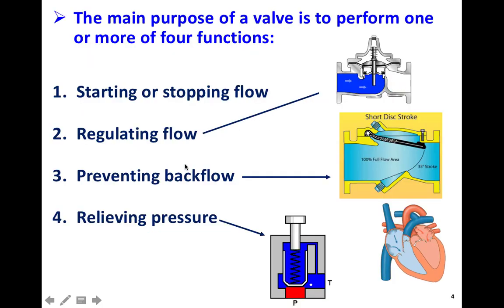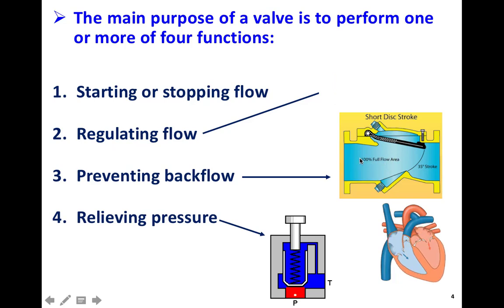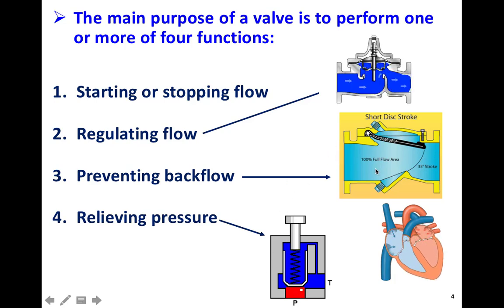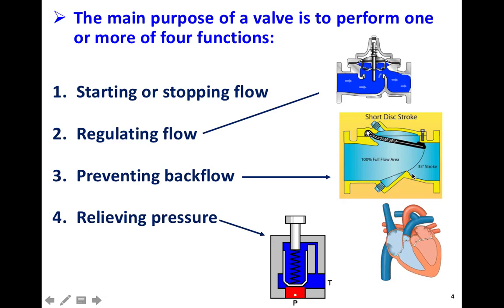Preventing backflow — we also call this a check valve. It is a valve that can allow the flow only in one direction. If we have a flow going from left to right, this gate is open. But once the flow is from right to left, this gate will be closed and it will block the opening of the pipe, and there won't be any flow from right to left. This gate can move from up to bottom.